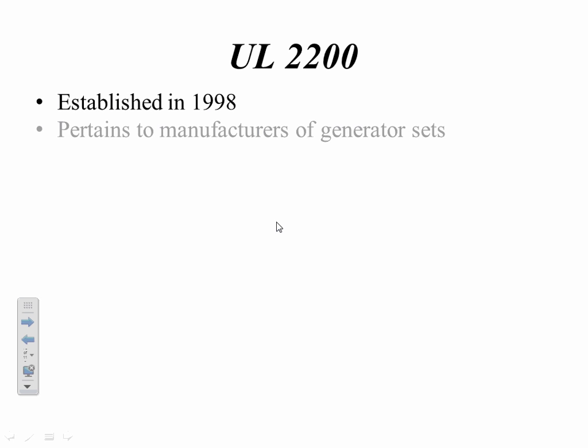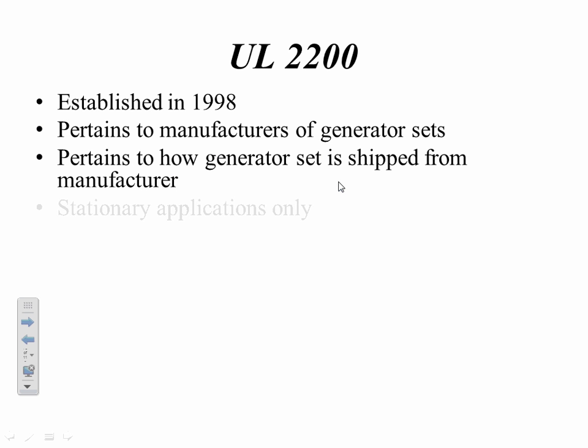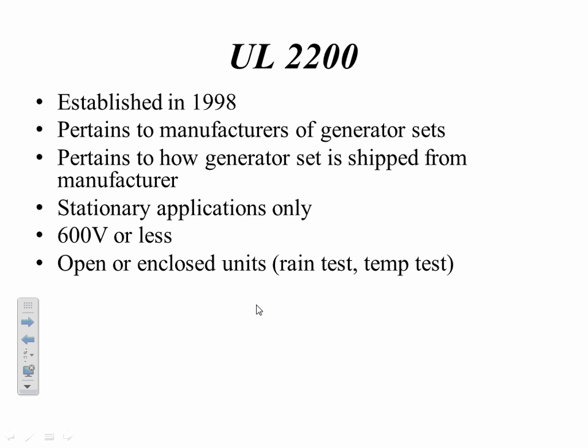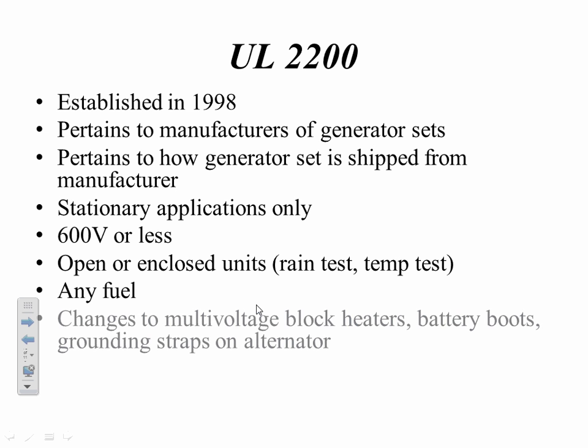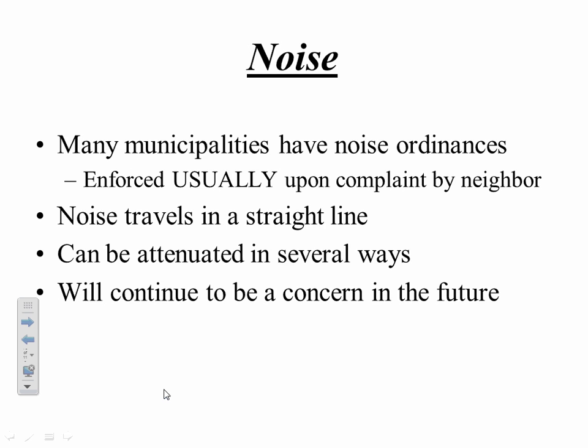Okay, we've talked about generators, transfer switches, types of loads. Other considerations that are out there are some codes. This one's getting a little dated. It's been around for a while. UL 2200. It was established in 1998. And this has changes that pertain mainly to the manufacturers of gensets. Caterpillar, Cummins, MTU, everybody out there. And it's how they're shipped from the factory. It's for stationary applications only. 600 volts or less, doesn't apply to medium voltage. Open or enclosed units the same. Any fuel. And changes to multi-voltage block heaters, battery boots, ground straps on the alternator. Has a lot of changes.